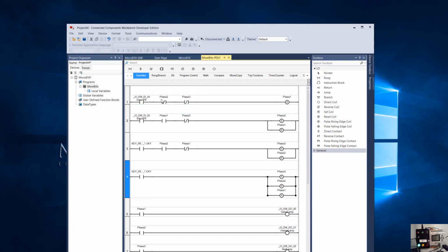You can see it. Rung 1 is the logic that gets us into phase 1. Rung 2 says, okay, if I'm in phase 1 and I'm not in phase 3 and I hit the black push button, I'll start phase 2 and I'll undo the bit that was keeping track of phase 1. The next rung just moves on one more level. If I hit the up key while I'm in phase 2 and I'm not in phase 1, then start the phase 3 bit and keep it high until I do something else and reset the phase 2 bit.